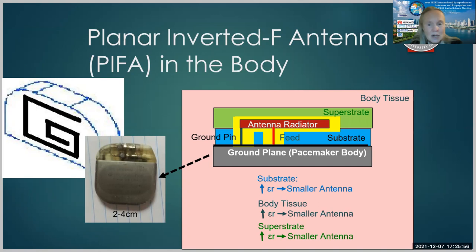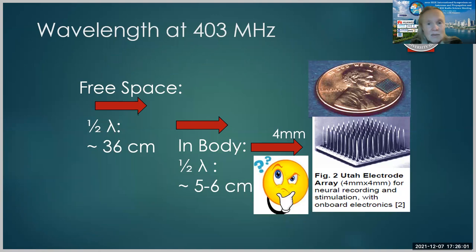But it remains a challenge when you want to stay in the same frequency so that you can have good penetration in the body, but yet you want to drop to a four millimeter size package. In free space, the half wavelength at 403 megahertz is about 36 centimeters. In the body, it's about five to six centimeters. But how can we shrink to get to four millimeters?